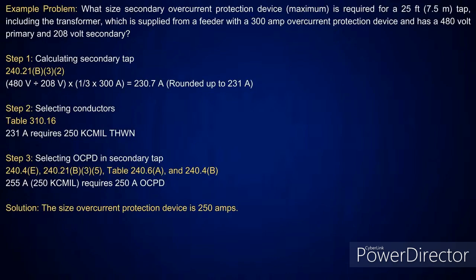Okay. So if I have 250 amps, I'm just going to protect the load that's there. That's 230 amps. I could put a 250 amp overcurrent device there. True, because the load is known. That's right. Load's known. All right.